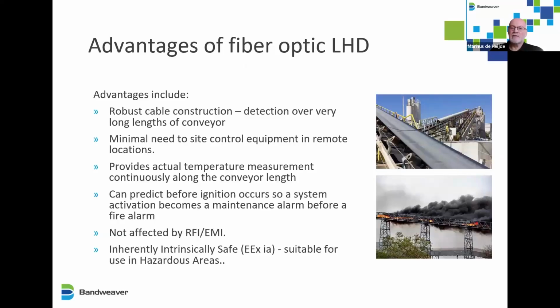So the advantages of fiber optic linear heat detection include very robust cable construction, which we'll look at later, and we can detect over very long lengths of conveyor belts. A minimal need to site control equipment, so we only need the cable in place in remote locations. And it provides an actual temperature measurement very accurately, continuously along the whole conveyor belt length.